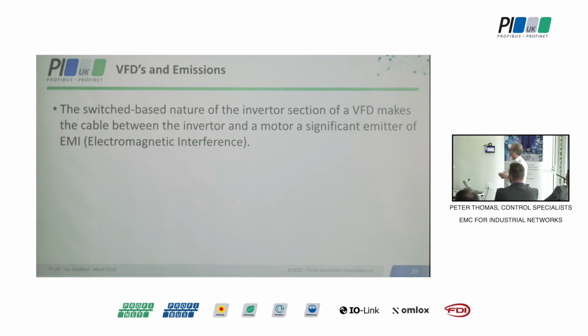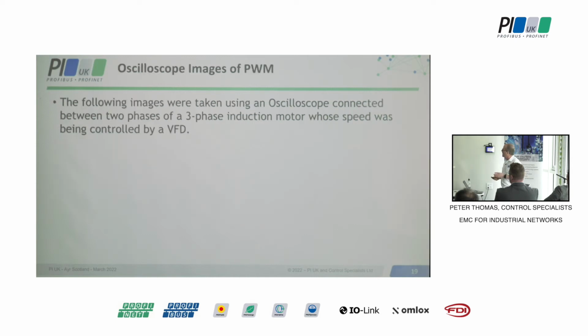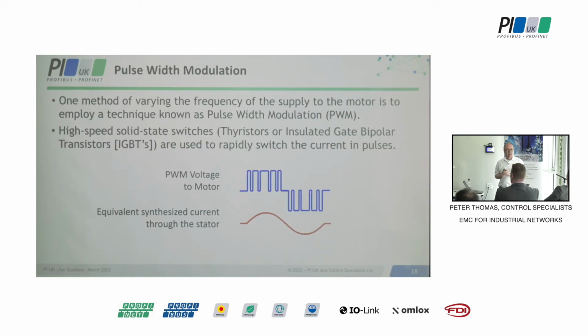Now, in this particular case, we've got some voltage switching on and off a lot faster than the current. So the kind of interference that we're likely to get from the motor cable is more likely to be capacitive coupling, because capacitive coupling is dependent on very fast changing voltages. The on and off switching is a parameter that you can adjust in the drive. It's called the carrier frequency.